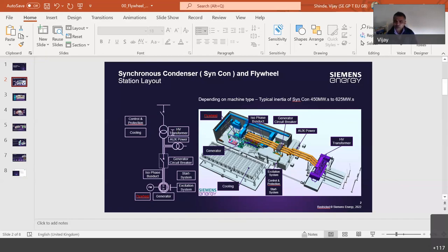So through the HV transformer, which is a step up or step down transformer, it is a low impedance transformer. Normal transformers you see on the grid are somewhere between 5% to 12% impedance range. This is a very low impedance transformer, less than 5%. What it offers is high current and high short circuit level to the grid. This is going through the point of wave circuit breaker and the rest of the auxiliary systems. So that in total offers the solution to the grid for grid stability, for short circuit level and reactive power control as well as inertia.